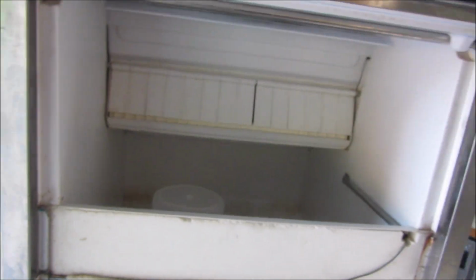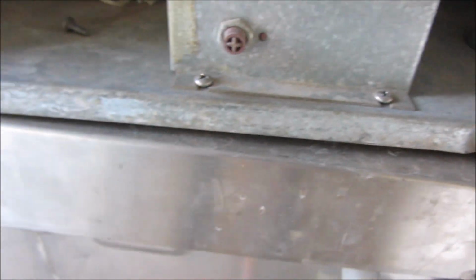What it's actually doing is freezing for so long that all the water in the bottom of this reservoir gets sucked dry, and the timer doesn't get notified that it wants to harvest the ice and start the timer. So I think it's the evap thermostat, which I've changed.